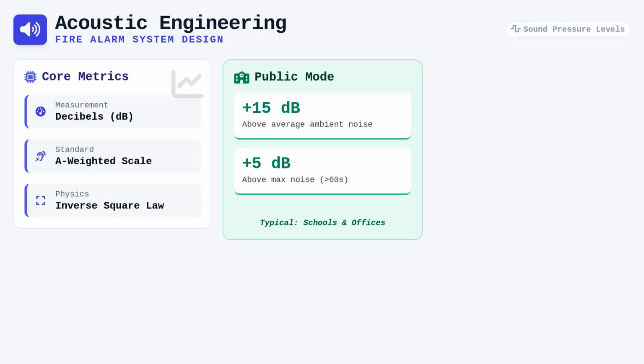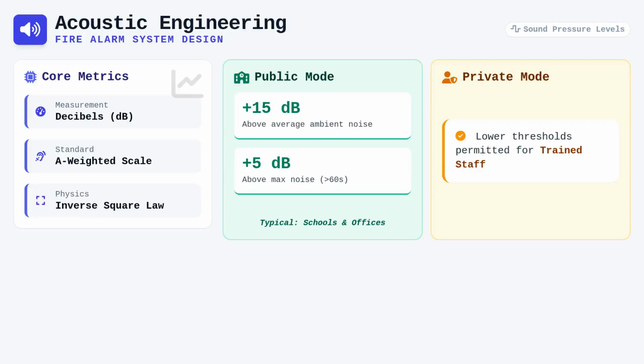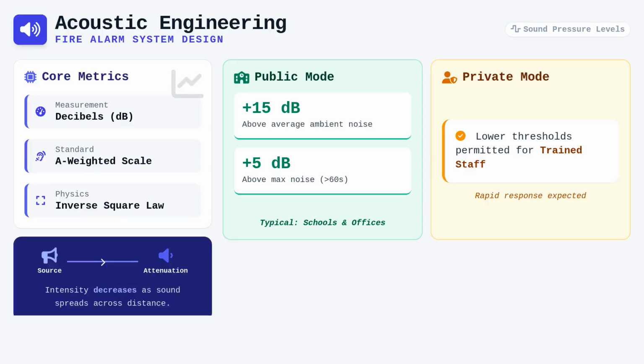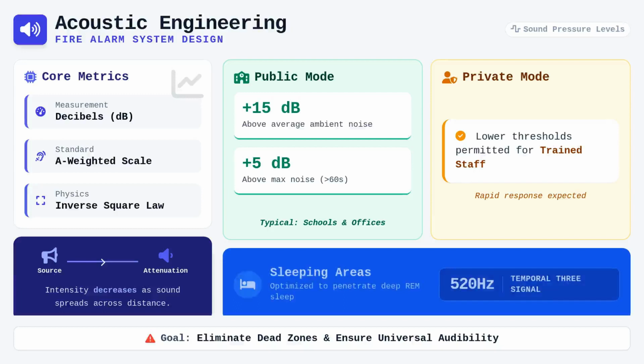Private mode, conversely, allows for lower thresholds if the occupants are trained staff who will immediately act upon the alarm signal. We must also account for distance attenuation, where sound intensity decreases according to the inverse square law as it spreads through the space. Achieving this balance requires careful placement of sounders to avoid dead zones while ensuring areas intended for sleeping receive the specific 520 Hz low-frequency temporal 3 signal required to penetrate deep REM sleep.